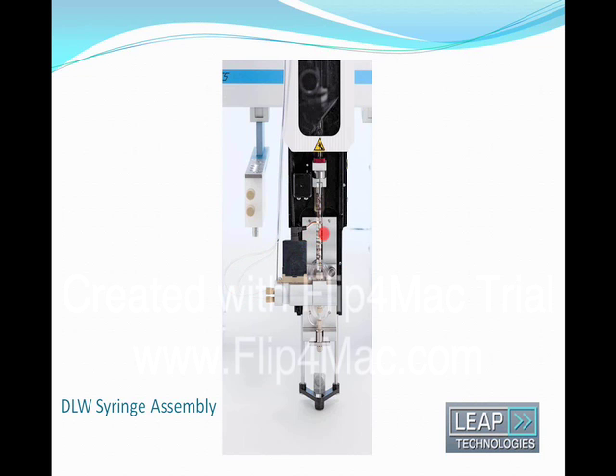A key design feature is that the two wash solvents are plumbed directly to the injection head right at the point where the retention loop is located. This means that there's a very low dead volume when switching from one solvent to the other. And under program control, it flushes both the retention tubing and the valve inlet.